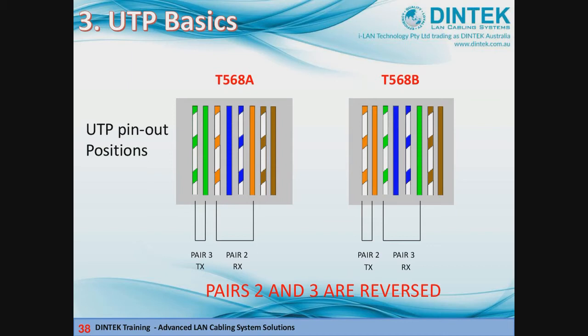Now for standards: there are 2 wiring standards under the TIA 568 standard, T568A and T568B. The difference is that pairs 2 and 3 are reversed - that is, the green pair and the orange pair are swapped, as you can see in this diagram. In Australia, we usually use T568A, but provided you stick to the same pattern at both ends, it'll still work fine. If you use 568A at one end and 568B at the other, you end up with a crossover cable.